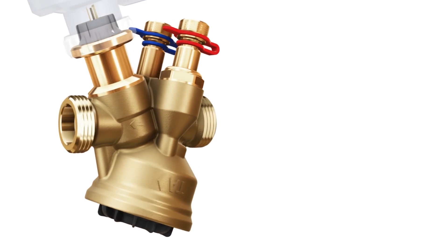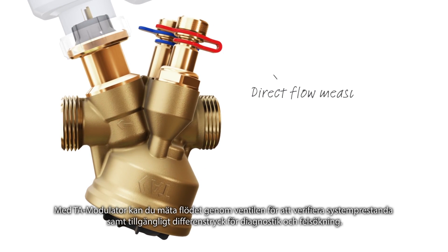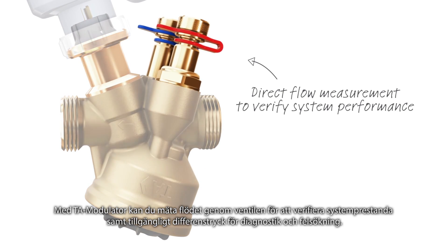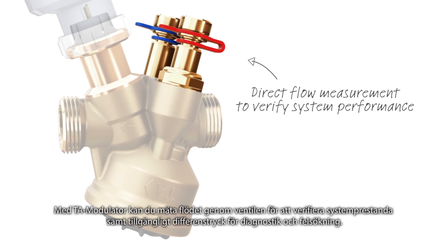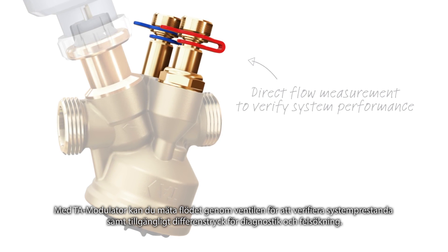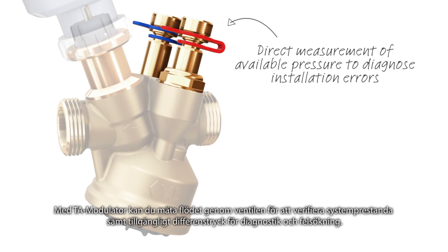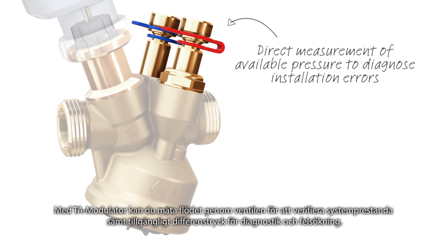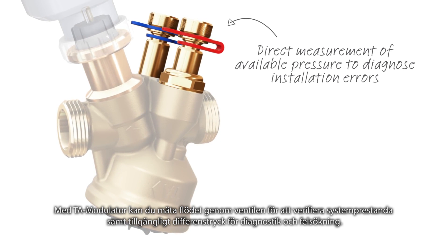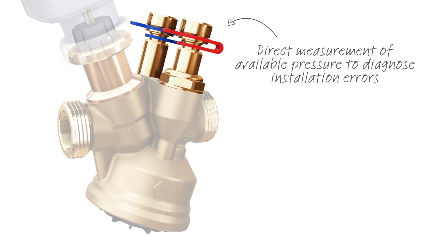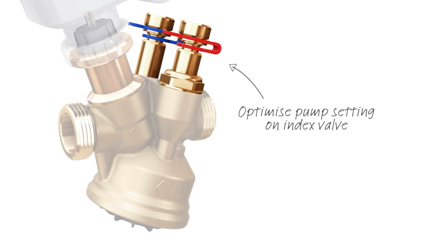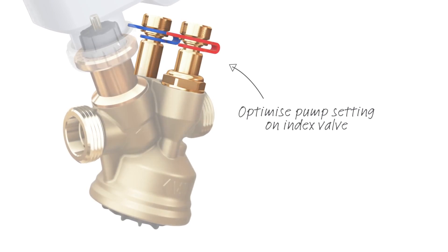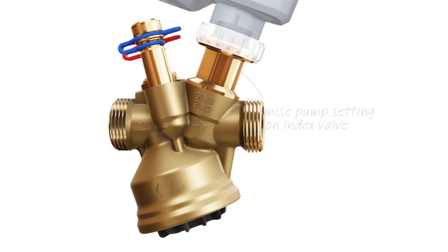With TA Modulator you can measure the true flow through the valve to verify the system performance, as well as measure the available differential pressure to diagnose possible installation errors. On the index valve you can optimize pump settings.